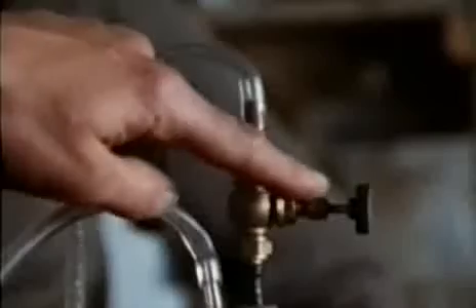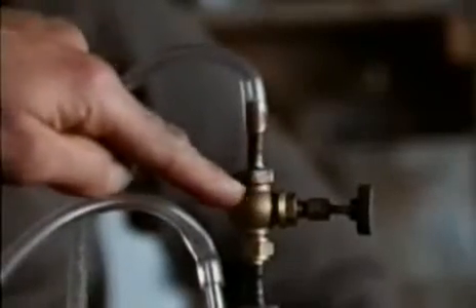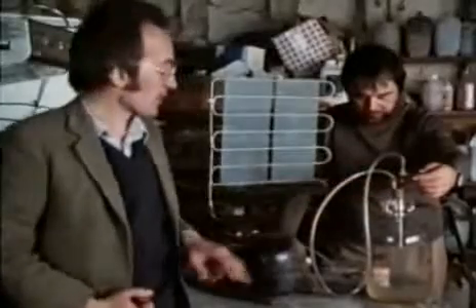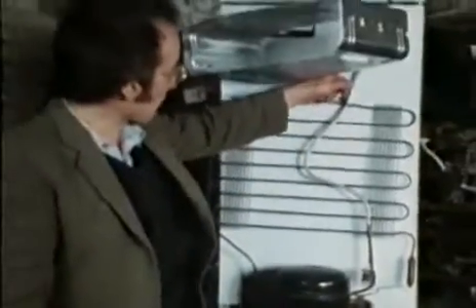The flow is controlled by this valve, just like the valve on the carbon dioxide cylinder. And in fact, early fridges had valves just like that, but we've been having great troubles to get the setting on the valve right. It tends to freeze up completely. In modern fridges, the valve has been replaced by a fine capillary tube. This has the same effect of restricting the flow. And to stop it freezing up, the tube runs up alongside the warmed gas coming back down again into the compressor.